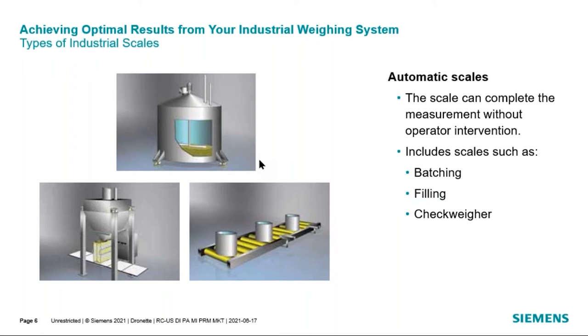With both batching systems and filling machines, they have two objectives: fill as rapidly as possible and hit the set point as precisely as possible. The way they do this is with multiple fill streams — a coarse fill stream and a fine fill stream. The scale electronics switch between coarse and fine. It starts out filling very rapidly and then when you get to say 90% of the desired amount, it switches to the slower fill stream to hit the set point as precisely as possible.